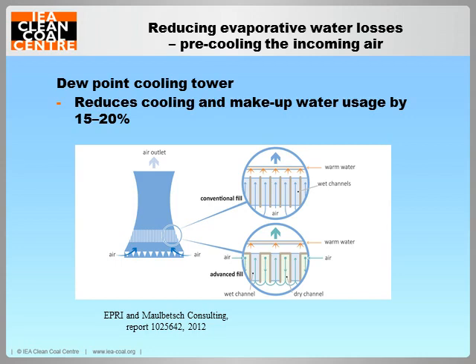Right, the warm water in the cooling tower is cooled to a value close to the wet bulb air temperature, which is a limiting factor for process cooling. Cooling to below this temperature could reduce the water lost through evaporation. And this could be achieved by pre-cooling the warm water and or the inlet air. One technology for pre-cooling the incoming air is the dew point cooling tower that's been developed in the USA.